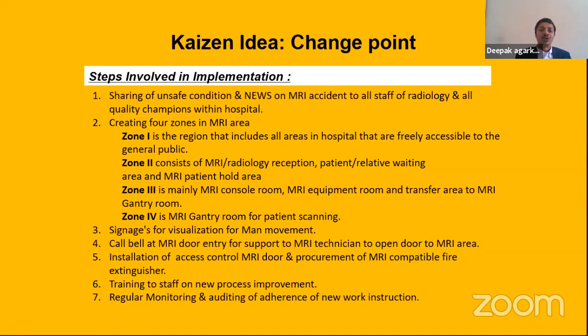The signages for the visualizations have been put. A call bell has been put for the magnet door entry. This is very, very important because access control has been given to the area to enter into the magnetic zone, but the technician may be busy with the scanning of a patient. So in order to ensure that he knows that a patient has come and is waiting, the nurse call has been put. And the procurement of the MRI compatible fire extinguisher has been taken.